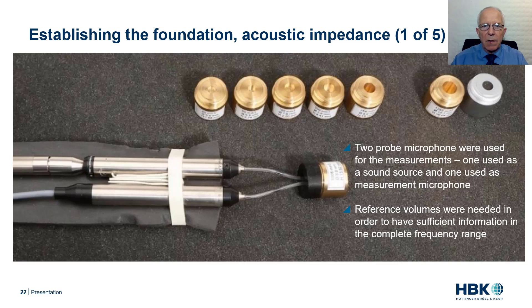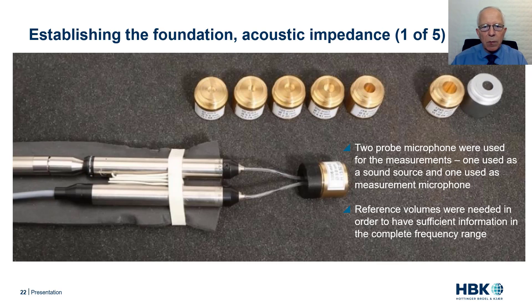The microphone arrangement used for the measurement consists of two probe microphones, which can be seen on the lower left part of the slide. One microphone acts as a sound source and the other is used as a measurement microphone. To ensure proper measurement results, several reference volumes — visible on the upper part of the slide — were needed to have sufficient information in the complete frequency range. In the photo, one of the reference volumes is connected to the microphone arrangement through two soft flexible tubes.